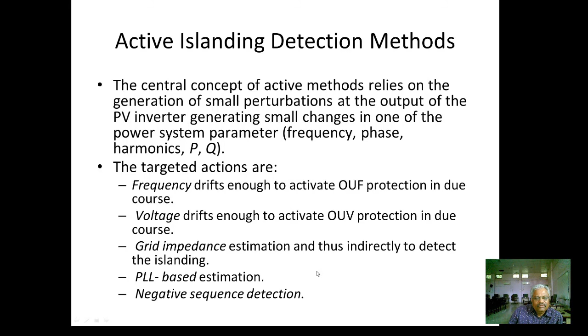The frequency drifts enough to activate OUF protection in due course when islanding takes place, or the voltage drifts enough to activate OUV protection in due course, or grid impedance estimation is used to indirectly detect the islanding. Other methods are PLL-based estimation and negative sequence detection. These are the cases of the active islanding detection method. The perturbation given to the power system parameter goes on magnifying after the anti-islanding situation. Now we will see these methods one by one.